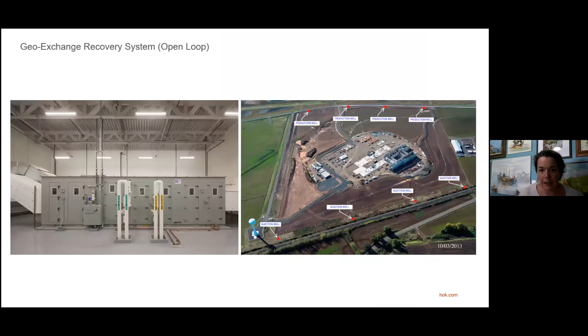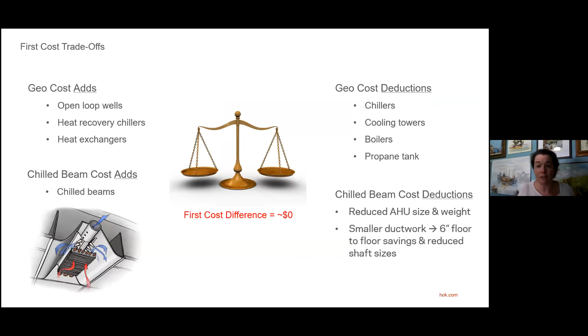Then there's the geo exchange, which pretty much eliminated other equipment needs. So we added costs with the wells, heat recovery chillers, heat exchangers, and chilled beams, but reduced costs by getting rid of chillers, cooling towers, boilers, and propane. We were able to reduce air handling unit sizes and weight, and use smaller ductwork because of the chilled beams and reduced floor to floor height. So we leveraged all of those things to come in not just cost neutral, but cost neutral on a really tight budget.